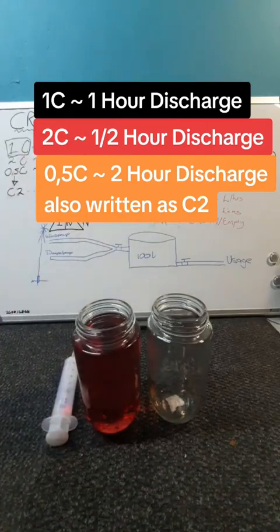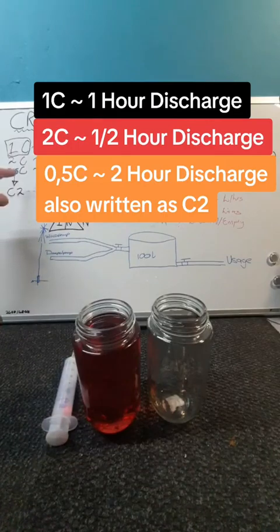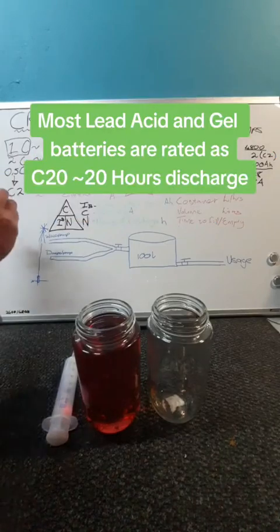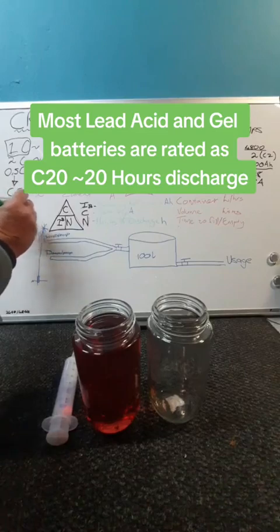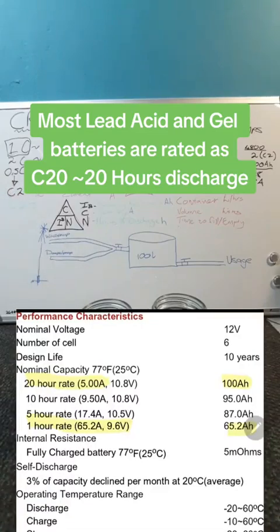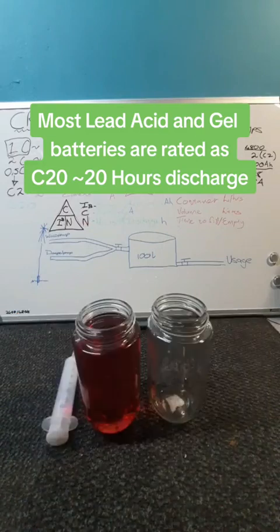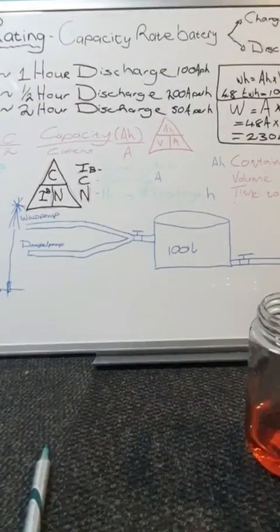Sometimes they will say 0.5C or they will say C2. But like a lead acid battery is basically C20, so that means a lead acid battery needs to charge for 20 hours and you need to discharge it in 20 hours. You can do it quicker but it will damage your batteries.